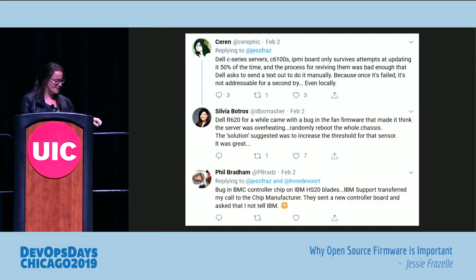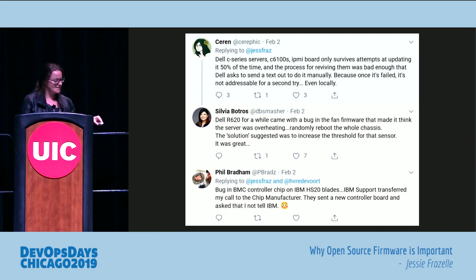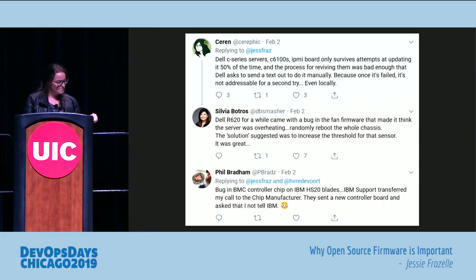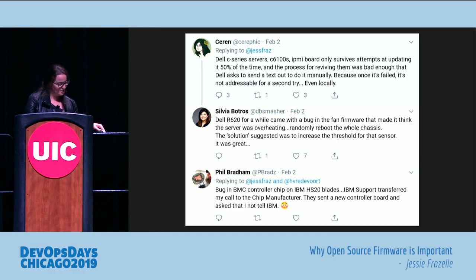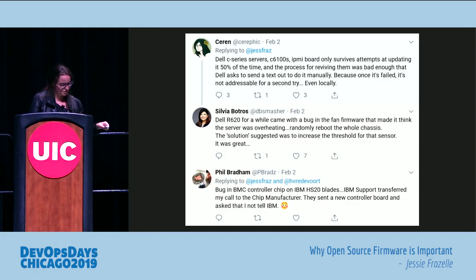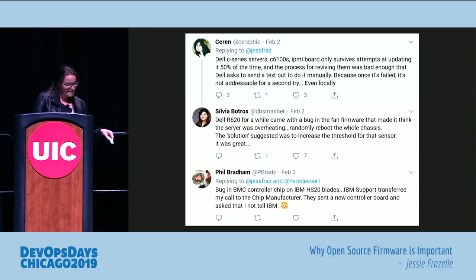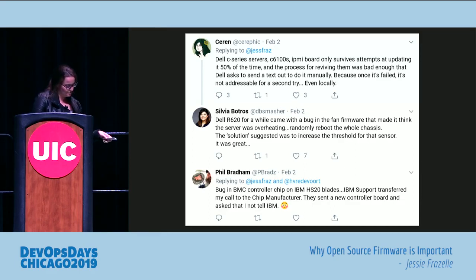Dell C6100 series servers: the IPMI board only survives attempts at updating it 50% of the time, and the process for reviving them was bad enough that Dell asked to send a tech out to do it manually, because once it fails it's not addressable for a second try even locally. Another Dell: came up with a bug in the fan firmware that made it think the server was overheating, randomly rebooting the whole chassis. The suggested solution was to increase the threshold for that sensor. Bug in BMC controller on IBM HS20 blades — IBM support transferred the call to the chip manufacturer, they sent a new controller board and asked that the caller not tell IBM. Absolutely horrifying.